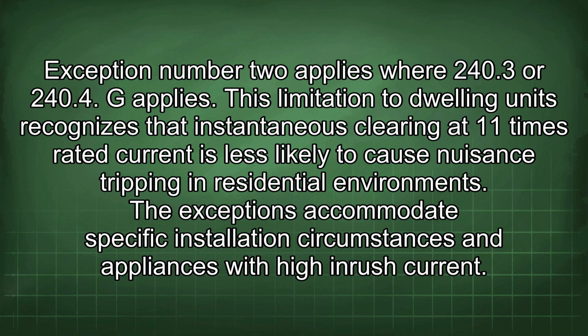This limitation to dwelling units recognizes that instantaneous clearing at 11 times rated current is less likely to cause nuisance tripping in residential environments. The exceptions accommodate specific installation circumstances and appliances with high inrush current.